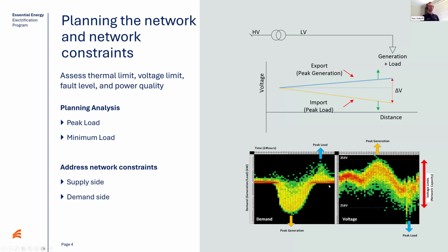I've taken one example around voltage assessments. Traditionally we'd focus the network on supplying peak load, so we'd be concerned with voltage drop. But now, with the uptake of renewables, we're looking at voltage rise during minimum demand as well. This is what we call widening of the voltage envelope.